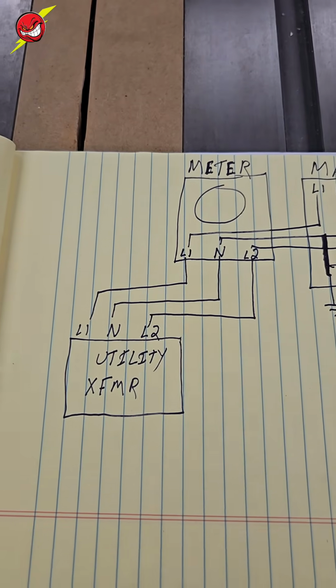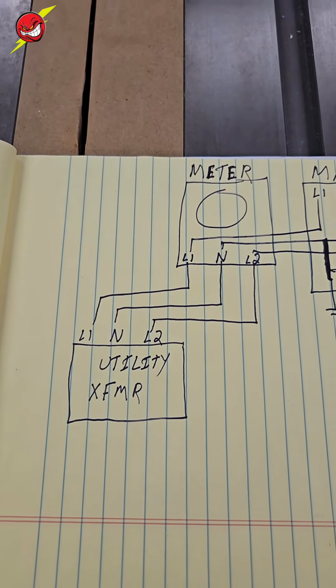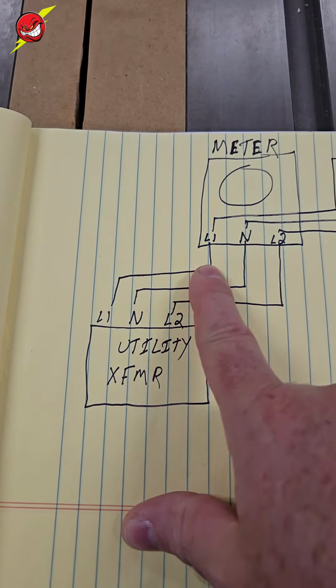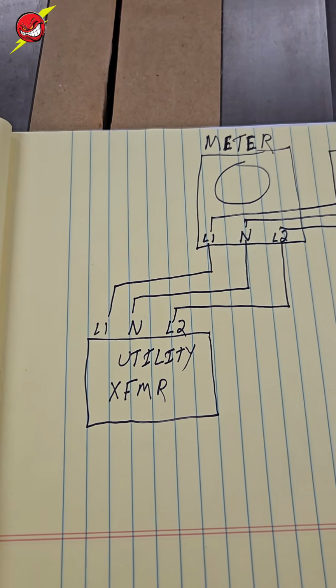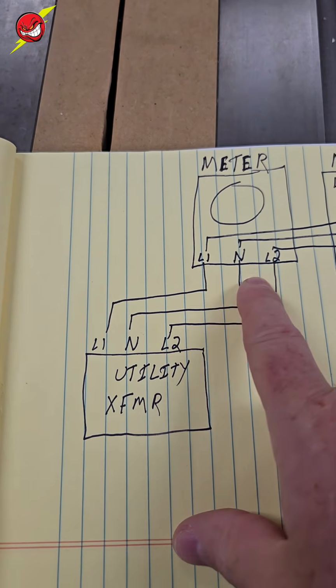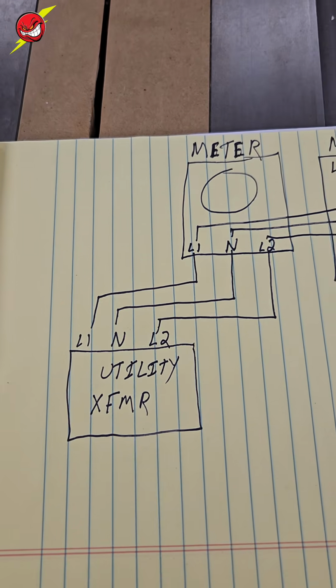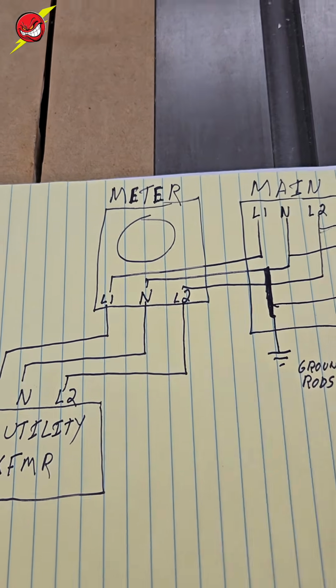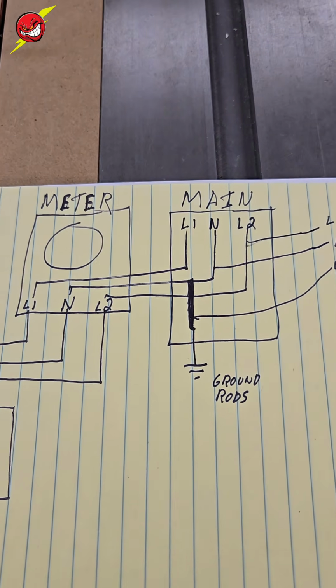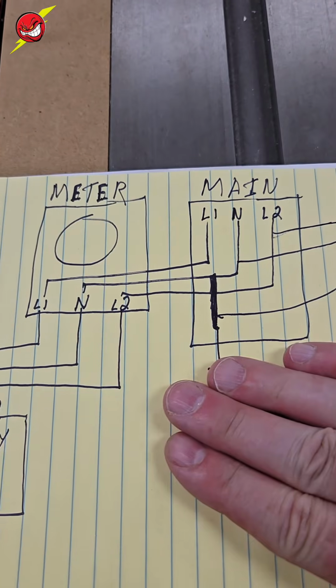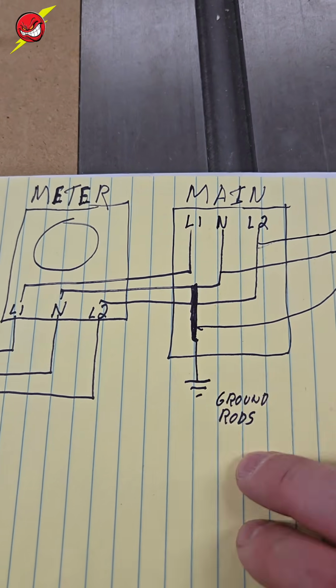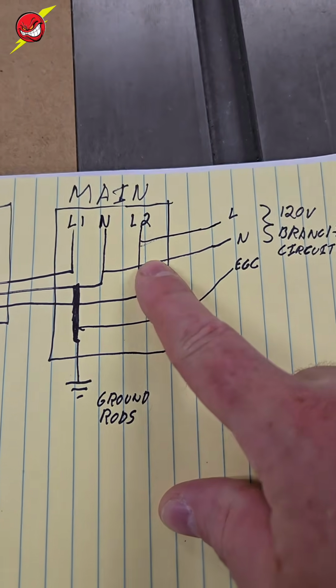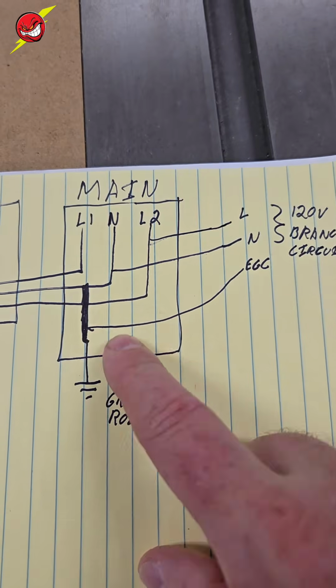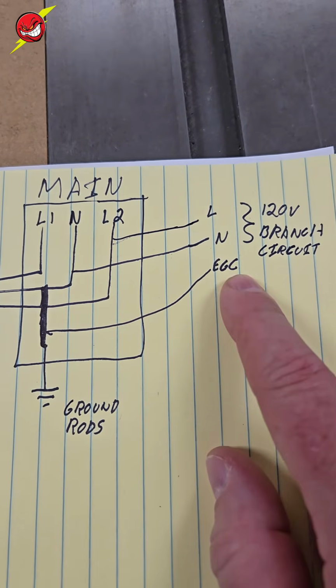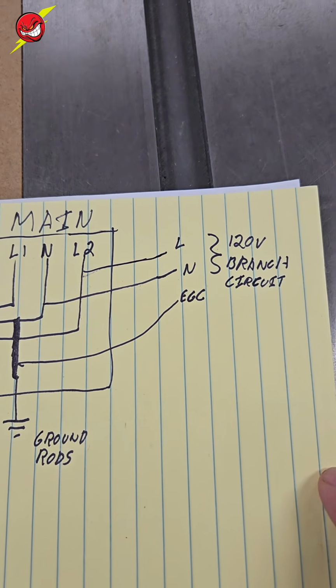How does a fault get back to the source? Well, let's take a typical residential service. We've got our two legs and a neutral. Our source is the utility transformer. So you've got your two legs, a neutral going to a meter base on the side of your house. From that meter base, it's going to go into your main panel or main disconnect. Ignore this portion for now. This is where you would drive your ground rods. Out of our main panel, we come off of L2, let's say, and a neutral, and here's our equipment grounding conductor for a 120 volt branch circuit.